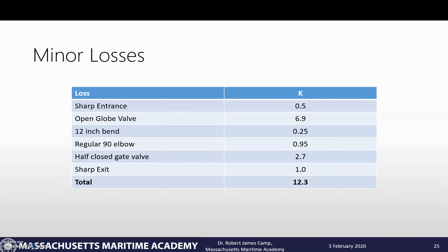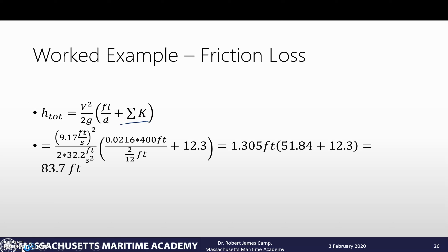At this point, let's calculate our total head. The total head is V² over 2g times (fL over d plus the sum of the minor K's). This is really the only new thing that we have in this problem. We just plug our numbers in: 9.17 feet per second divided by twice gravity, so 2 times 32.2 feet per second squared. The units here will end up being feet, which is what we expect.